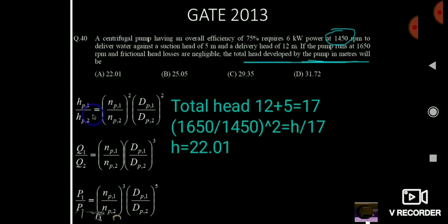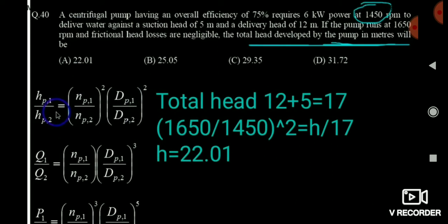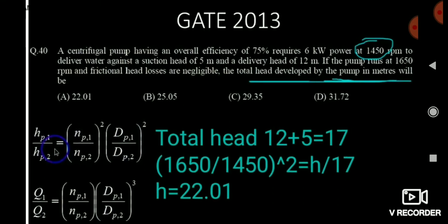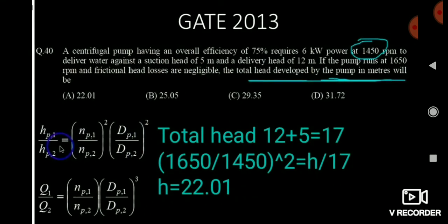Calculate the total head, which is 17 meter. N1 = 1450 and N2 = 1650 RPM are given. Since head is directly proportional to N², using H2/H1 = (N2/N1)², we can calculate H2 = 22.01 meter.